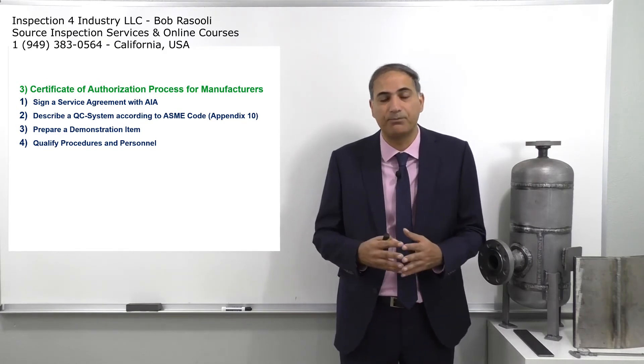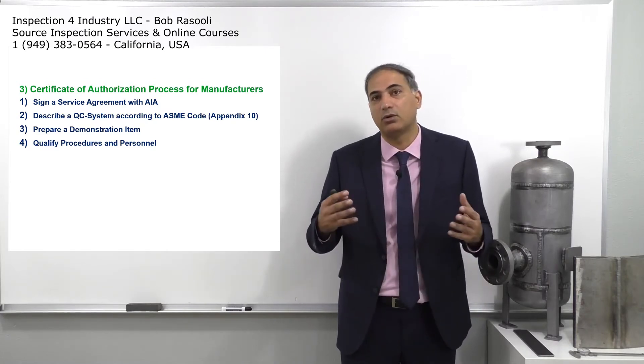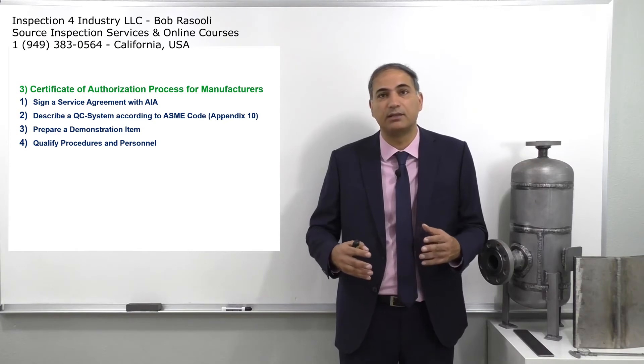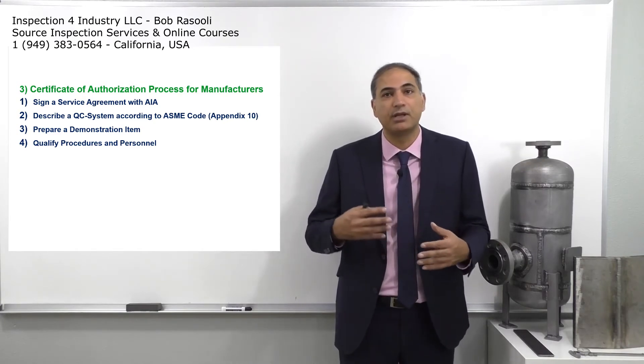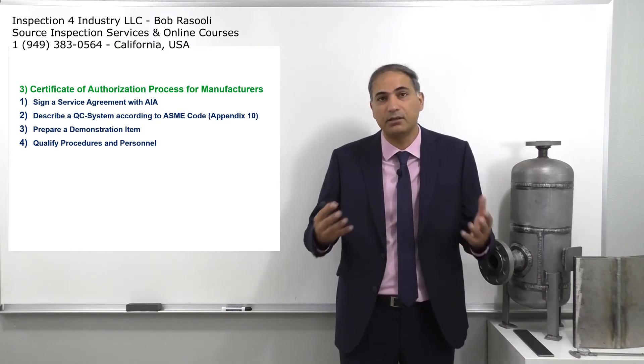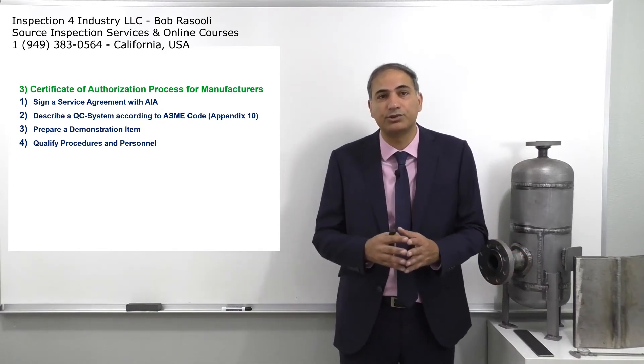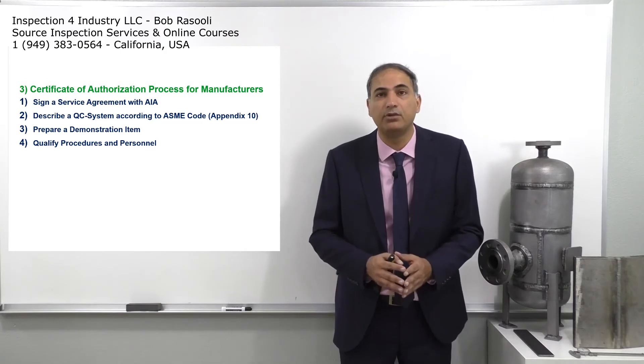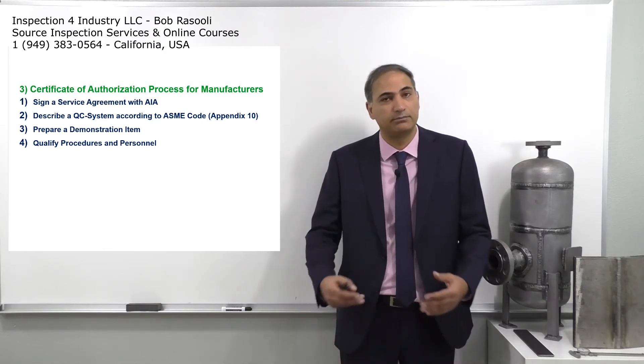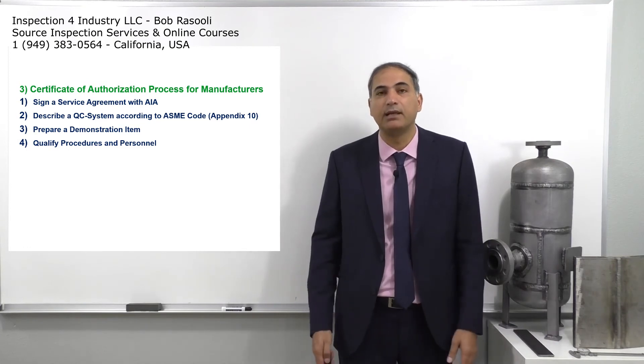Number four is quality procedures and personnel. Any pressure vessel manufacturer needs procedures such as welding procedures and welder or welding operator performance qualifications. They also need hydrostatic testing procedures, and personnel qualifications for welding and NDE. All of these must be ready to be presented to the auditors from ASME or the Authorized Inspection Agency.